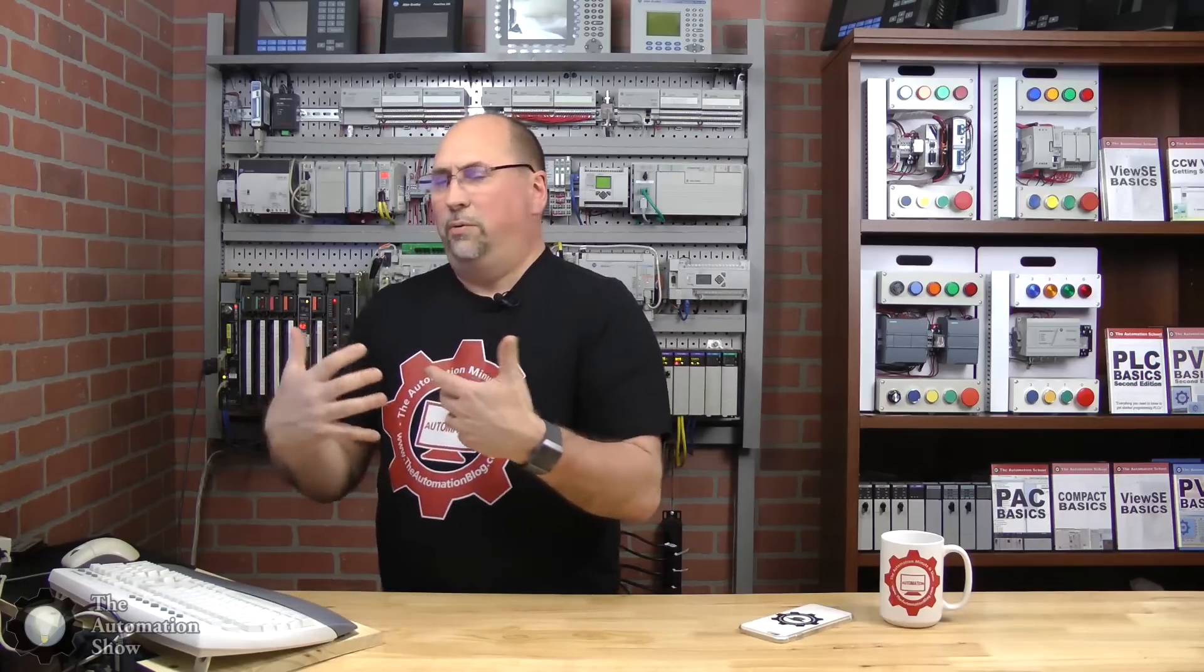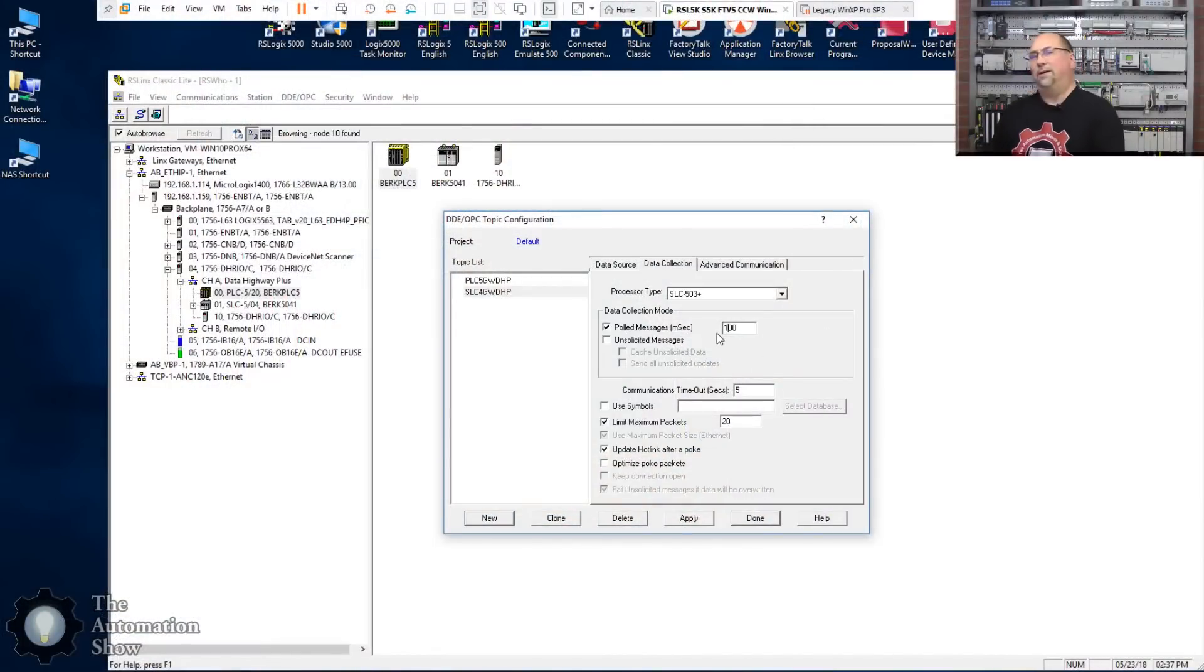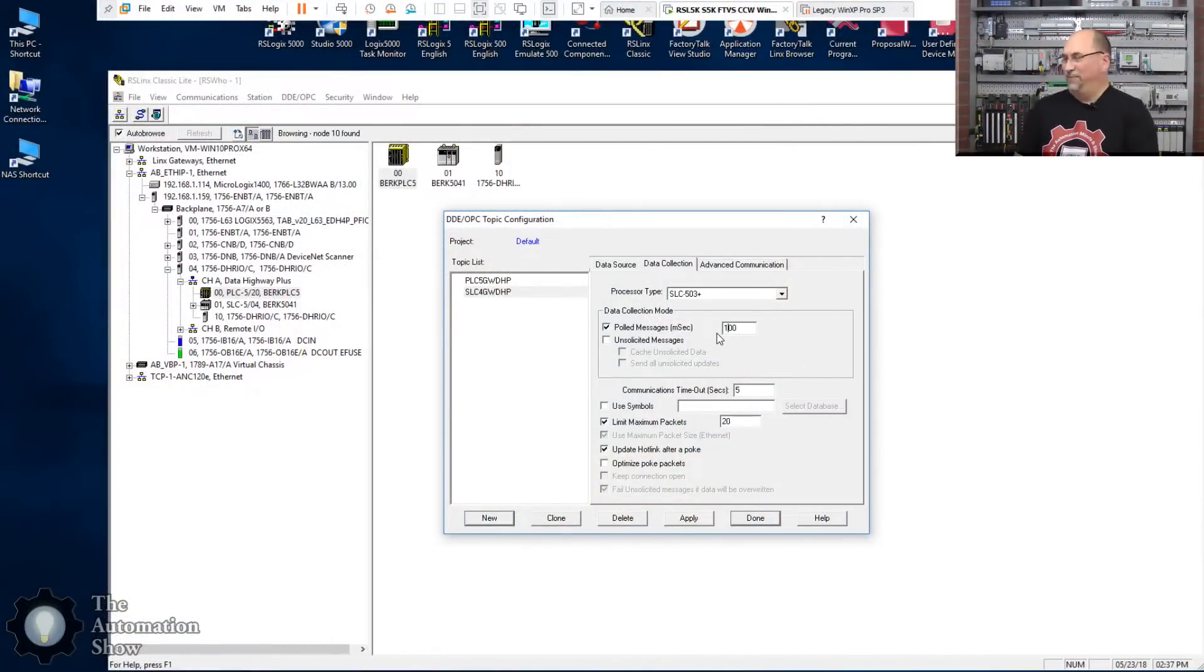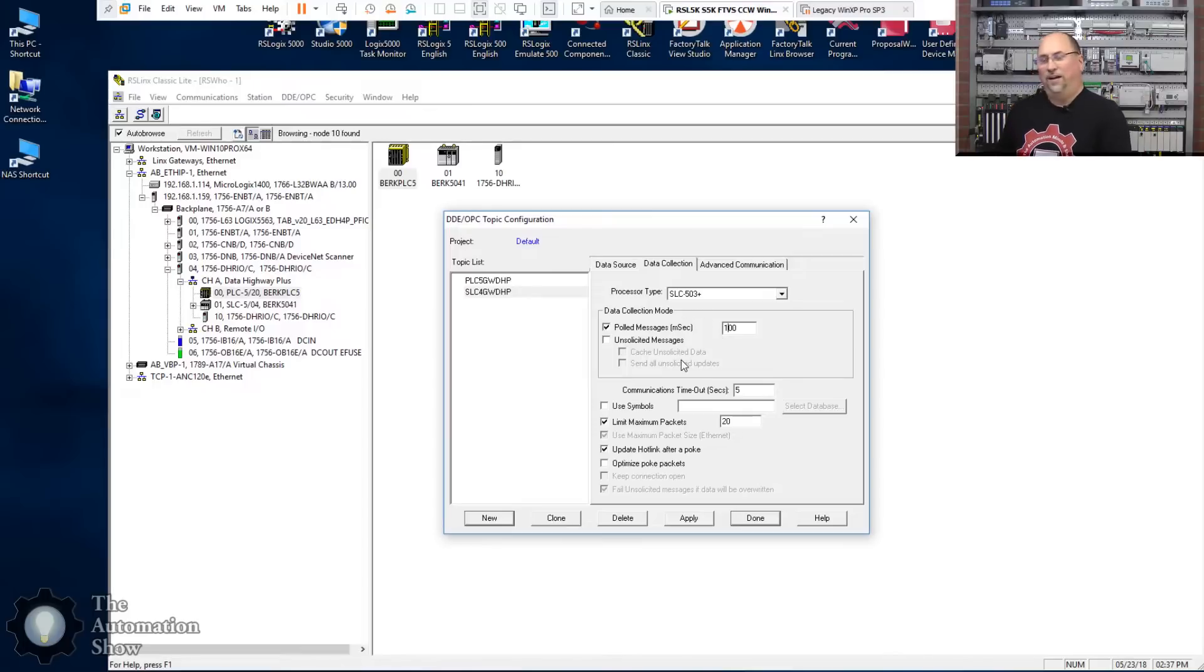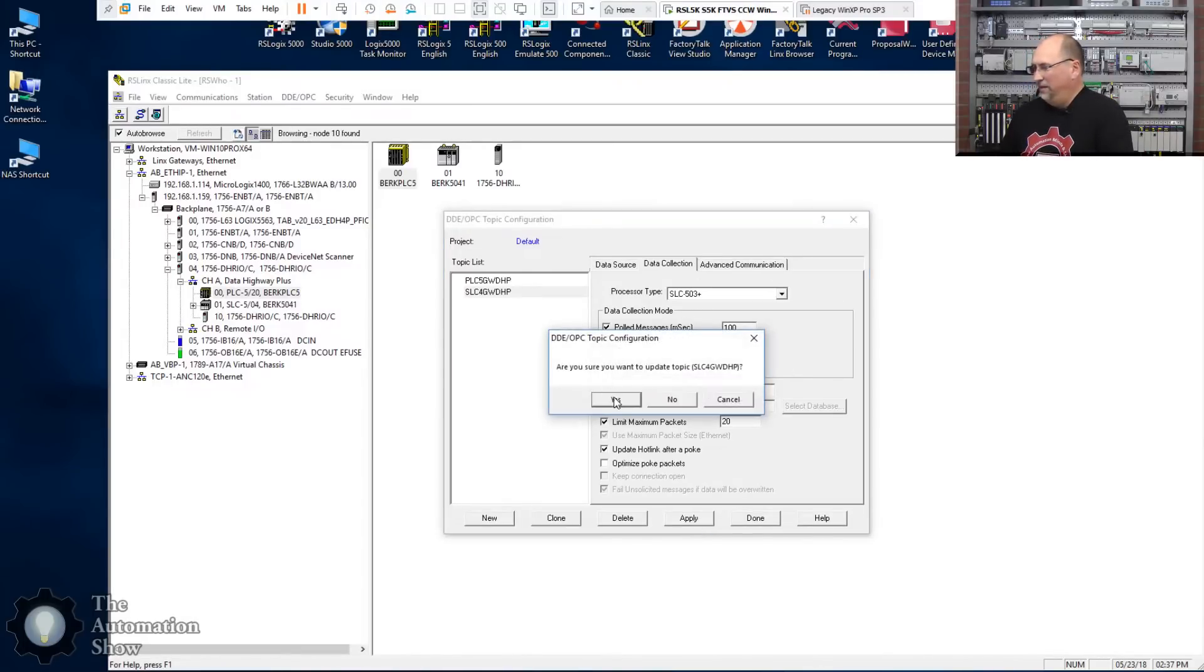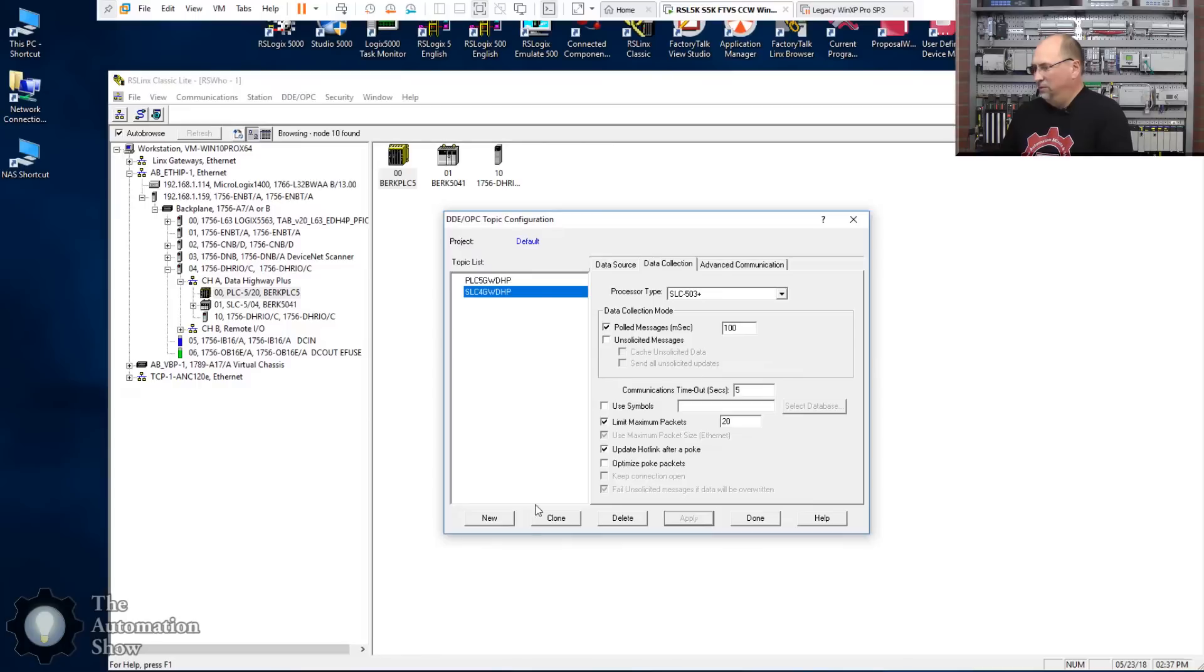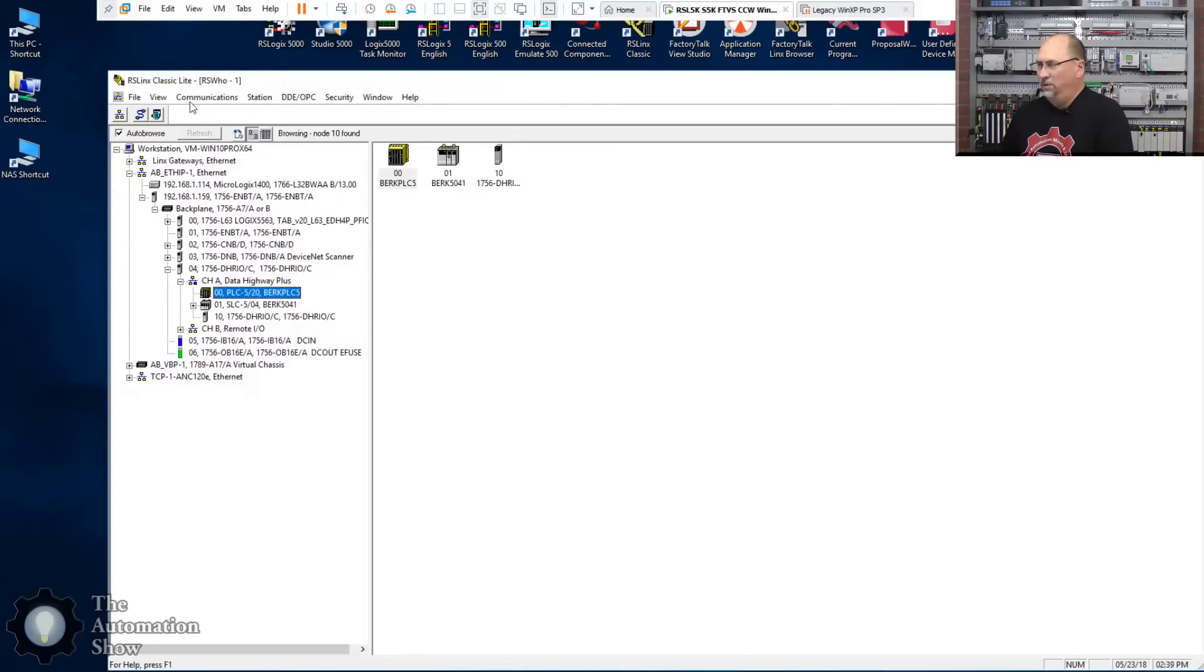So if you have a Data Highway Plus, it's slow, and you have a lot of panel views on it, it's probably because of that reason. But in any case, if you're doing like starting motors, starting systems with an HMI, I have found that if you go slower than 250 milliseconds it just feels laggy. It can take a second or two from the time you press the button to something changes. So I always felt like you have to have it under a second round trip, and the only way to guarantee that is to do about 250 milliseconds or 330 milliseconds. But in any case, we're going to set ours to 100 milliseconds because we're just working here on the bench and we can go super fast. So we'll do that and we'll hit apply. Yes, good.